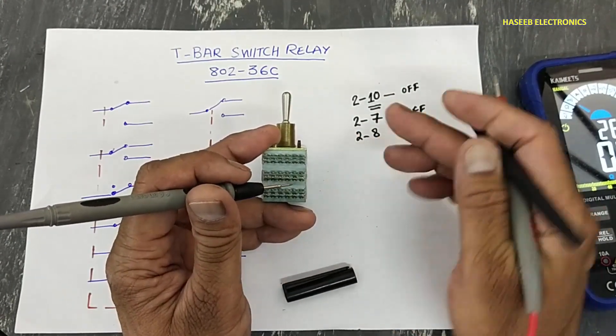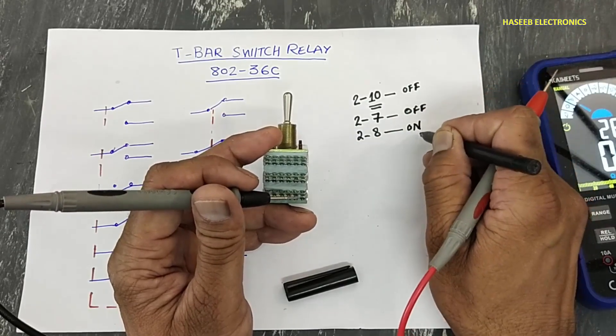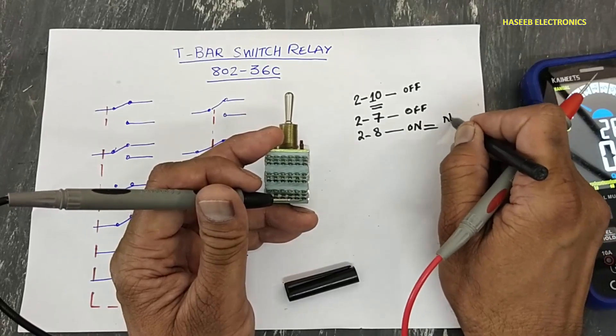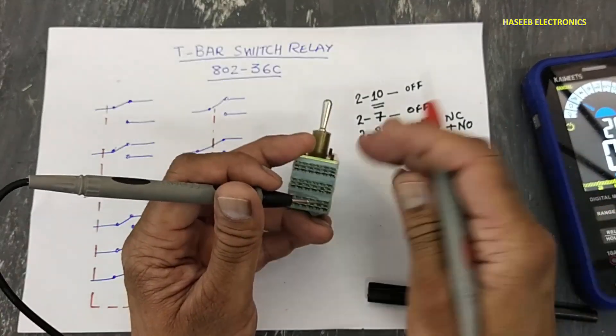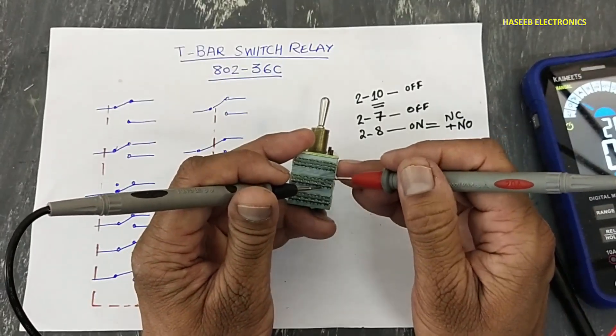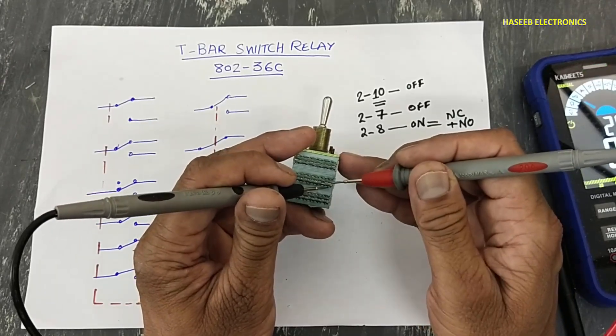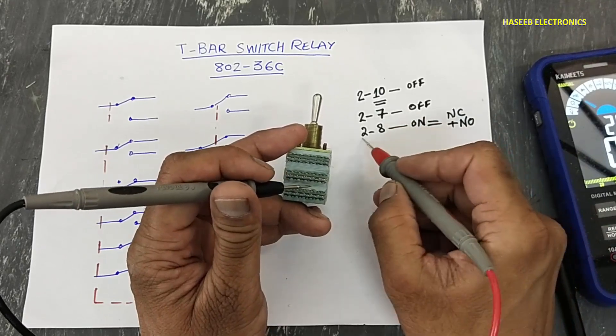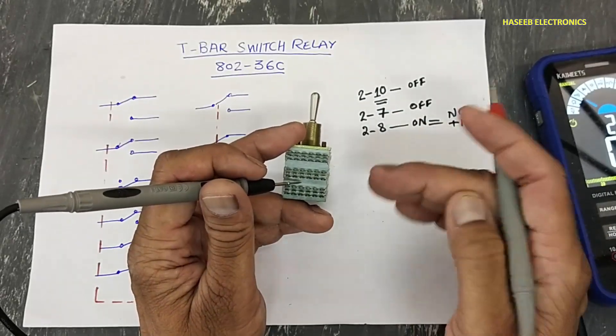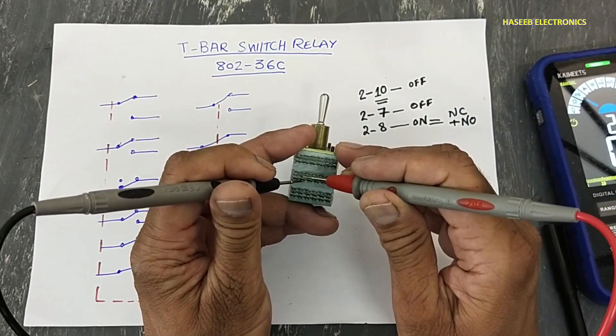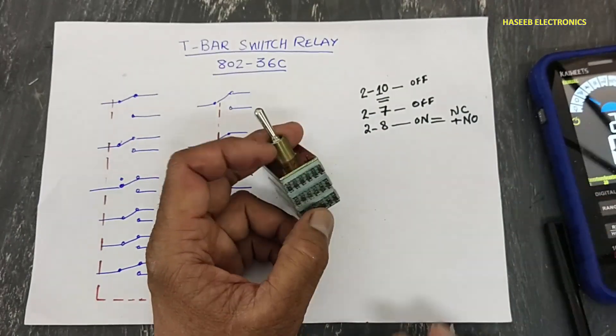Stage number 2, switch number 8 in ON condition is making connection with both points. Contact number 10 is working in OFF condition. Contact number 7 is working in OFF condition but it is making a problem for both directions. The other stages are good; we have a problem in these three contacts — how can we overcome this issue?